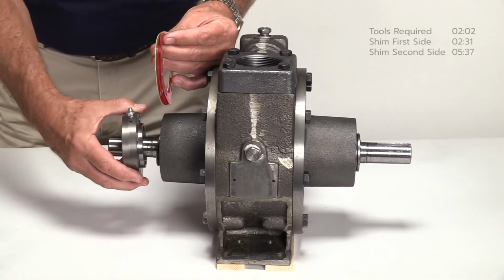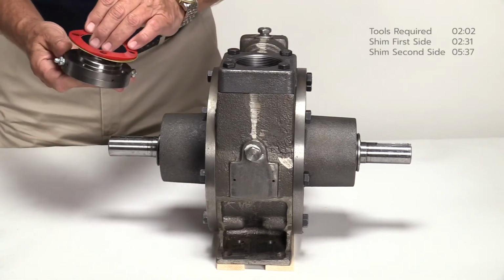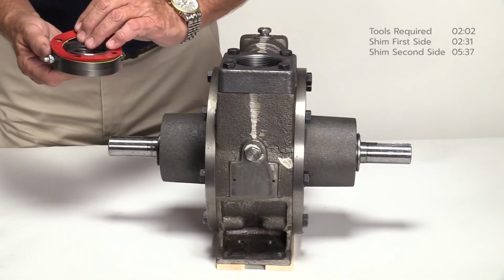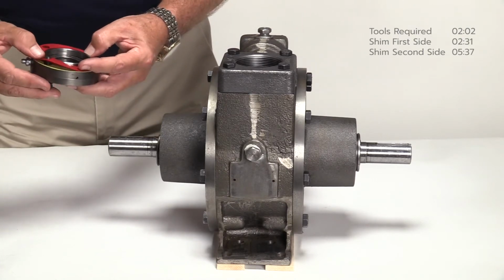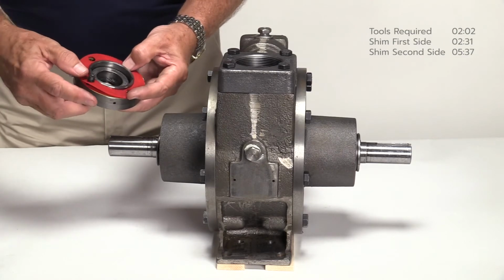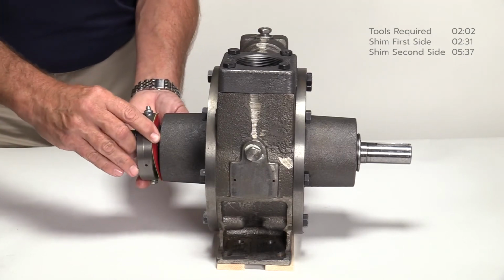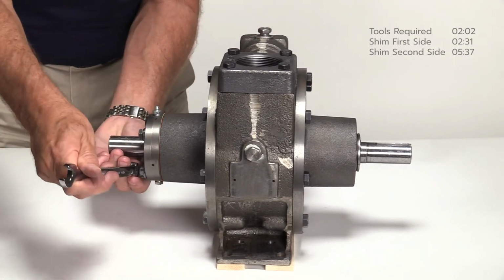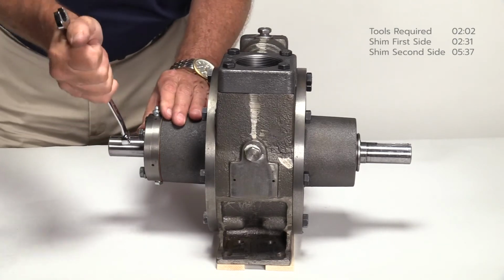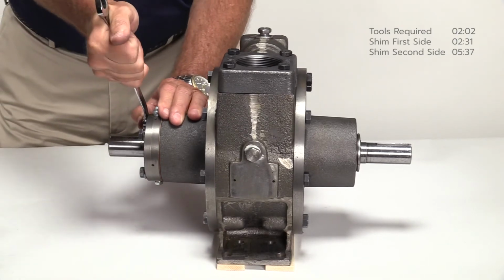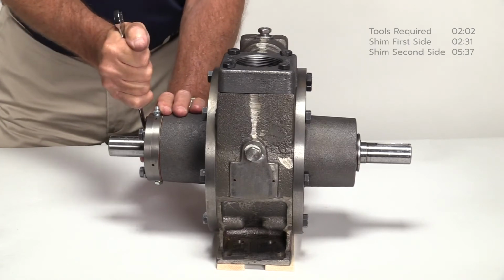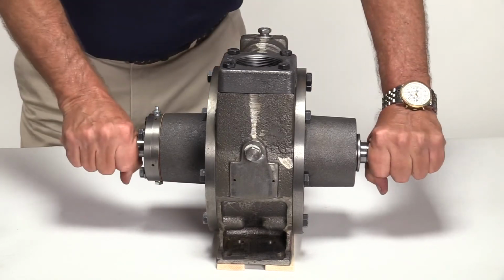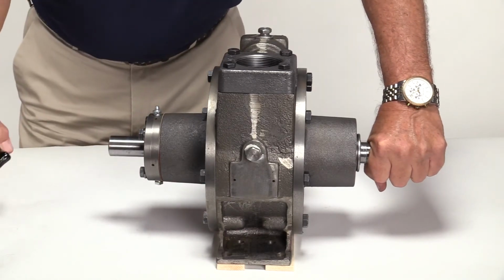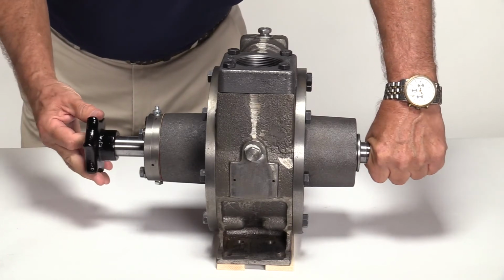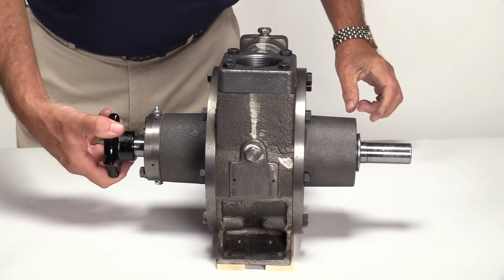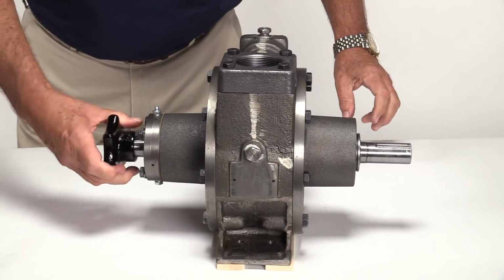Remove the bearing cap and add the 30 thousandths shim pack. To hold the shims in place, insert a bolt through one of the holes in the bearing cap and slide it over the shaft. Install the remaining bolts and tighten in a cross pattern to the torque value listed in the Installation, Operation, and Maintenance Manual. After the bearing cap has been secured, make certain the pump shaft turns freely by hand. Now repeat these steps on the opposite side of the pump.